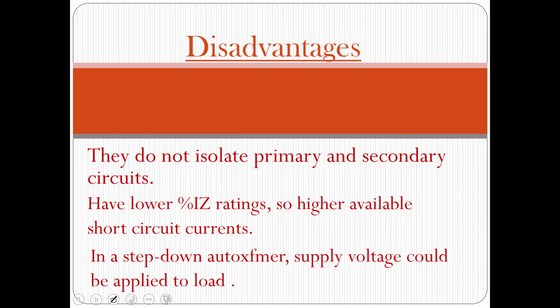Some disadvantages of an autotransformer now: they do not isolate primary and secondary circuits, so where we need isolation, you cannot achieve that with an autotransformer. They have a lower percent IZ rating. What does that mean? They're going to have a higher short circuit current availability. And in a step-down autotransformer, the supply voltage could be applied to the load if we have some sort of fault in our transformer.